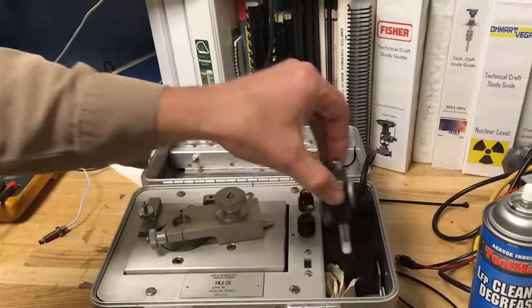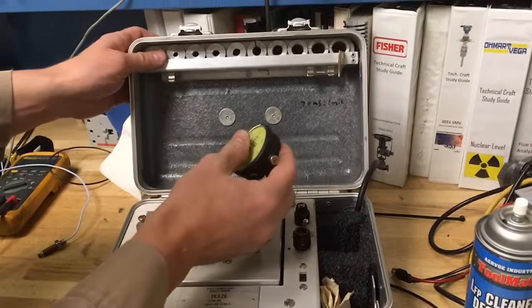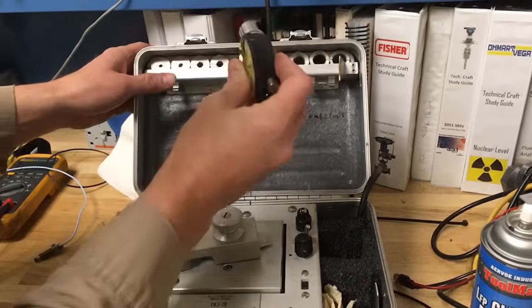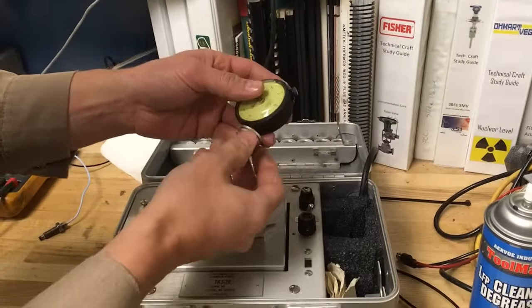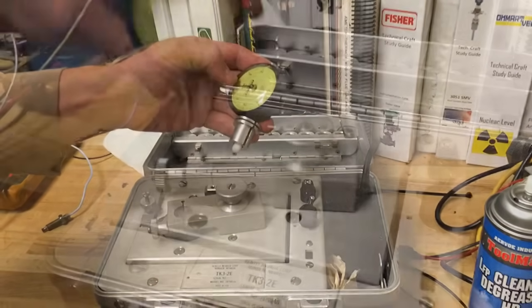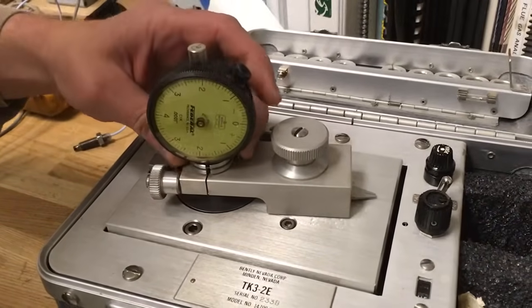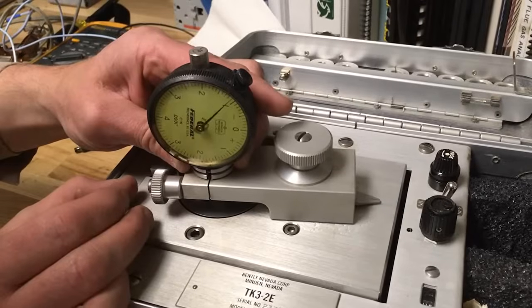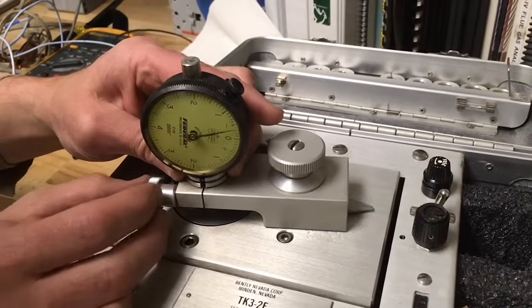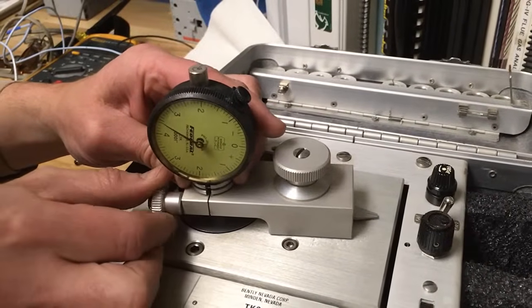Next, locate the bushing that fits the dial indicator and install it in the swing arm. Ensure the split of the bushing lines up with the split of the swing arm clamp. When you place the indicator in the assembly, let the plunger bottom out, then lift approximately ten thousandths of an inch. Secure the dial indicator by tightening the receiver.